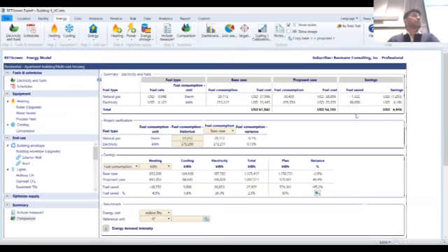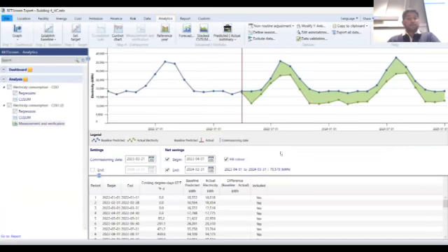So hooray, we saved more than what we predicted, which is 70,578 kilowatt hours. That's your M&V for lighting. Why do I stop here? Because out of the 3 measures that I implemented, lighting was one of the only measures that would save a lot of electricity.